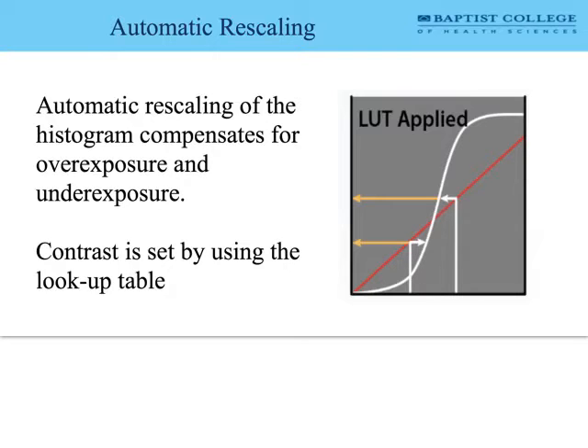For automatic rescaling, the values of interest are predetermined, and the automatic rescaling makes data output and image display consistent even when there are errors in exposure technique. Rescaling can create an acceptable image despite overexposure, meaning the technologist has no visual cue that overexposure occurred — this is what we call dose creep. Automatic rescaling is the number one culprit. It's actually very helpful, but we must understand there's no visual feedback to determine whether an appropriate technique was used. Dose creep is the potential to gradually increase patient radiation exposure over time due to that lack of visual feedback.